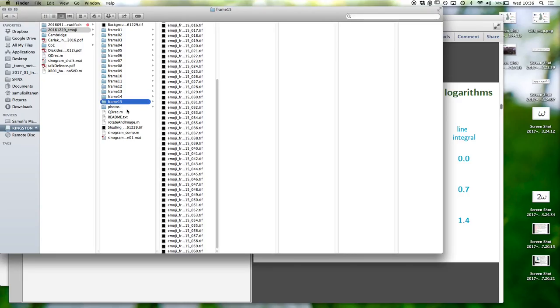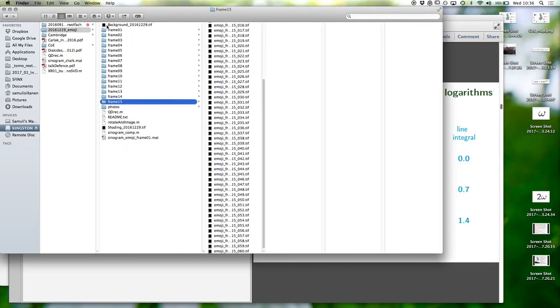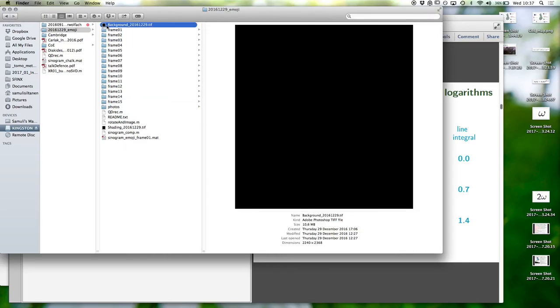When measuring, two calibration images need to be taken. These two calibration images are called background and shading. So this is one of the images coming from the detector.